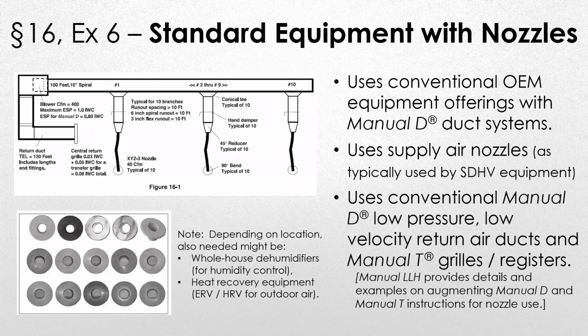And then probably what most of us are looking at, and probably will be the most prevalent system used, is using standard equipment with nozzles. So Manual LLH will tell you how to use or adapt Manual D towards the different pressures and pressure drops that we'd have in this type of system, as well as it goes into detail about picking supply air nozzles and sizing them correctly per Manual D.